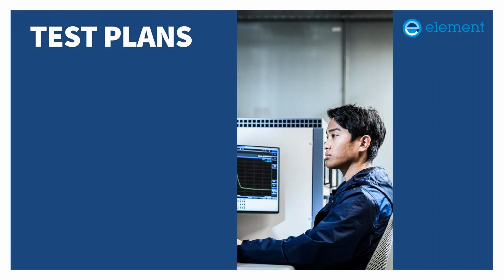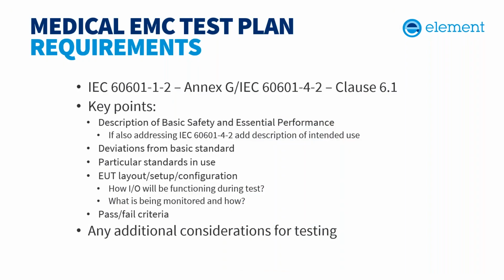So you might think you're ready to test, and then a test lab asks you, do you have a test plan? So what's a test plan, and what is needed in a test plan? A test plan basically lays out the goal of your testing, details of your device, and any special additions or changes to the base standards. IEC 60601-1-2 Annex G covers what is required in a test plan, and in -4-2 it's clause 6.1.